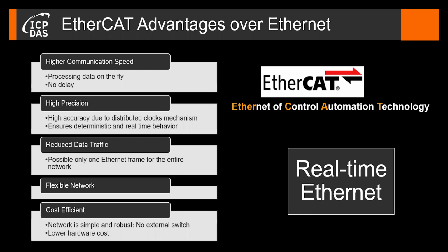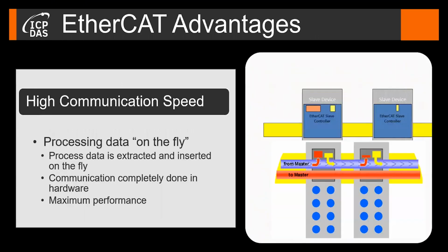So EtherCAT is optimized for precision machine control. Its high data load and efficient data transmission reduce the data traffic on the network, prevent data collision, and ensure short cycle time. It is a flexible network which supports all types of topologies. This is a cost-efficient network with low cost of implementation. EtherCAT is developed as an open standard. The protocol is now supported by dozens of vendors of servo drives, remote I/O blocks, actuation, and sensing devices.